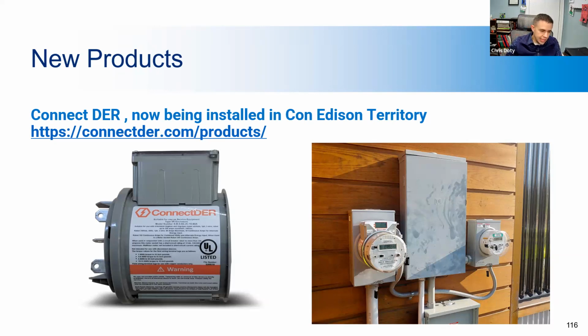It can help them forecast how much power they're going to need from power plants and all of that. And it can eliminate costly interconnections, sorry, and reduce installation errors for supply side connections. This was, as I said, experimented with in the Con Ed territory. This is installed by the utility. It's the point of interconnection for the PV system. And like I said, it gives the utility real-time solar generation data.